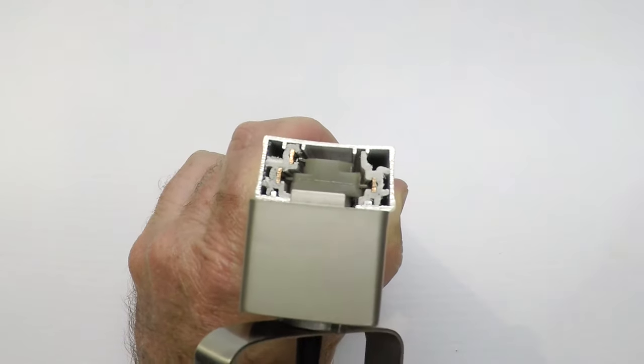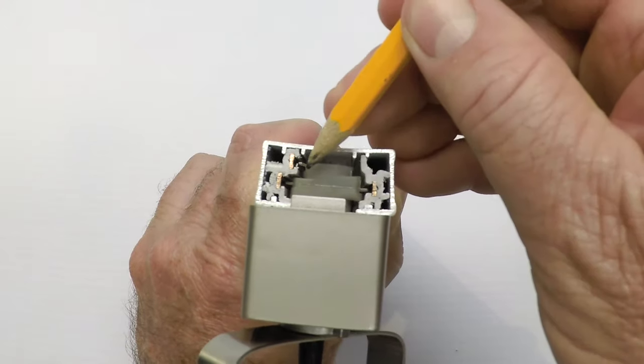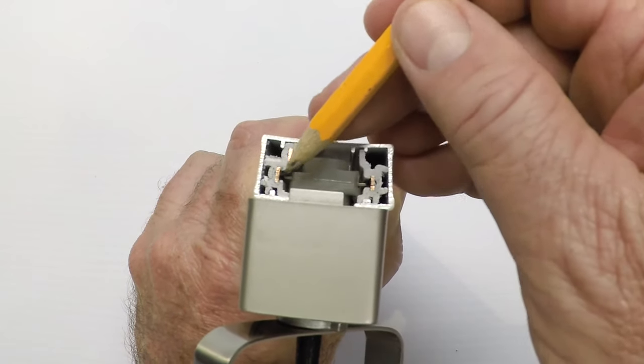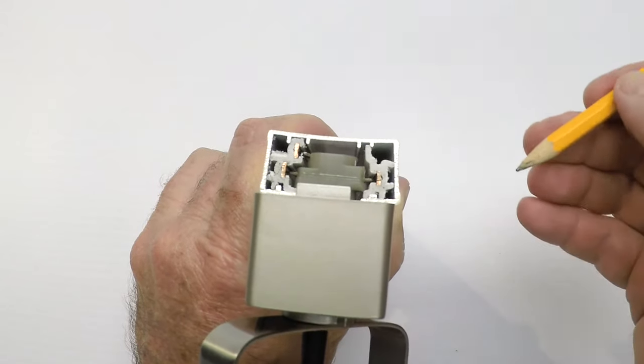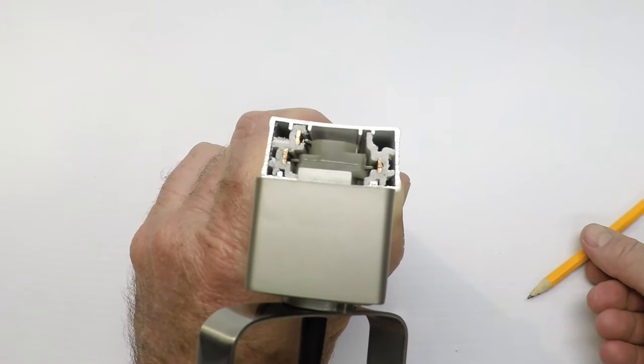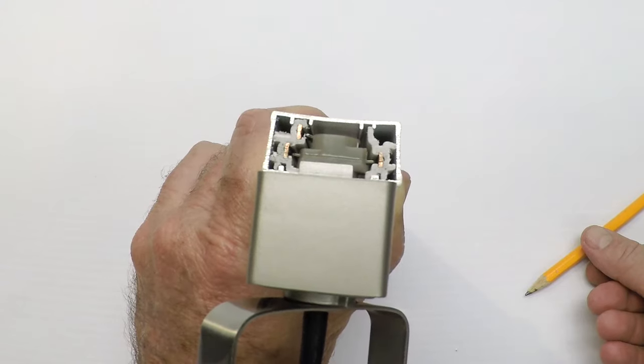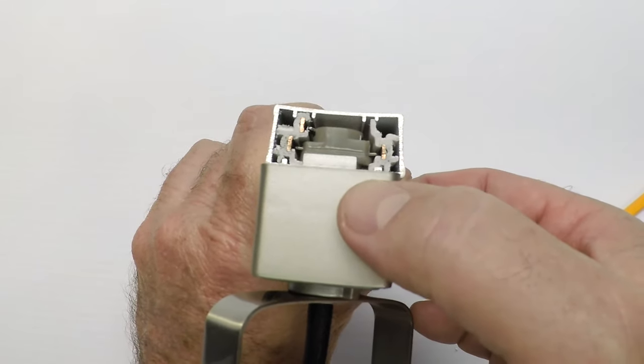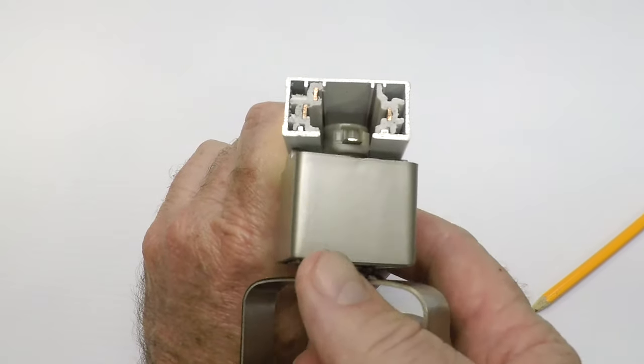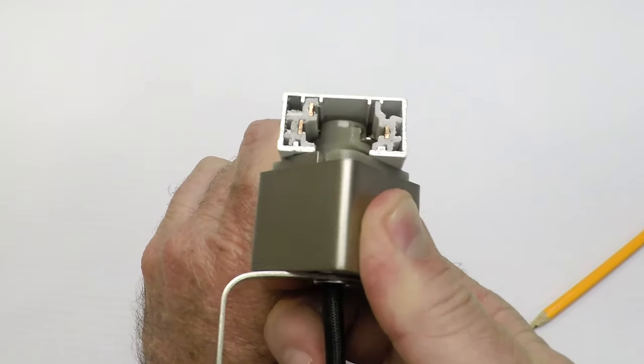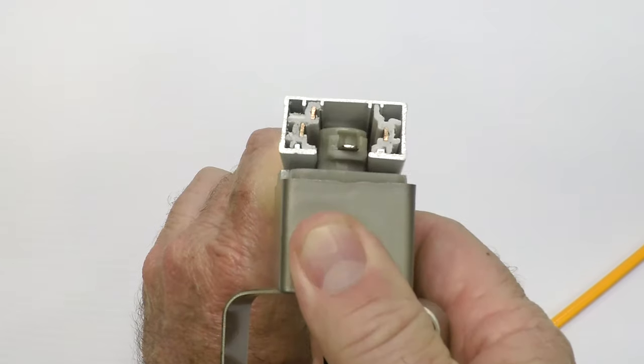Here I'm going to see if I can bring this up even tighter to the end, hopefully you can see that down inside there. So the hot is connected to the hot bus bar, the ground is hitting ground, and the neutral is hitting neutral. These bus bars are held in little plastic channels which are made to float inside your light fixture. This is the proper way to put a light fixture in: not slide it in from the end like we did today, but actually you're going to put it in, pull the shroud back, and rotate the light fixture.